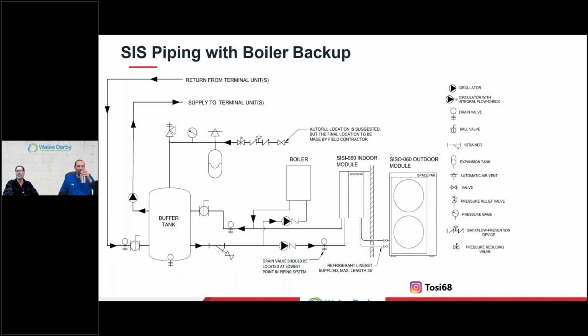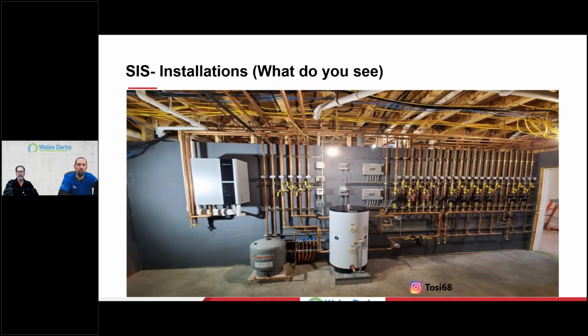All right, so this is what the split could look like. Again, line sets coming from outdoor to indoor. We have our magic box or module or SIS. You can see we're pumping to a buffer tank. Look halfway between the buffer tank, there is a boiler, right? So again, if the house load requires something higher, if it ever gets cold enough out that 120 doesn't get it done, well, we can just turn on a boiler. We can turn on multiple things, okay? And that buffer tank again becomes a source for all things internal. This is a good snapshot of what a split system looks like.